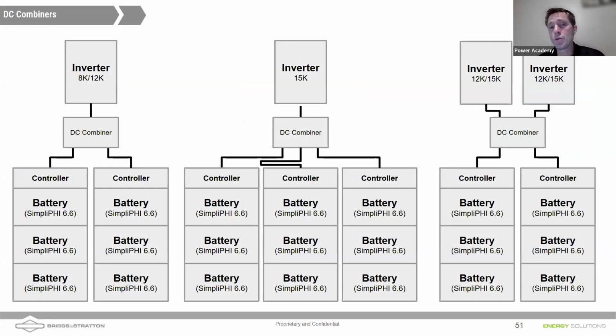If you've got more than 2 stacks with a 15K, like 3 stacks as you're seeing there, you'll want to use a combiner as well, and you'll want to make sure that you have overcurrent protection on each of those stacks. And so then you'll come out of that DC combiner and feed the Sol-Ark 15K there.